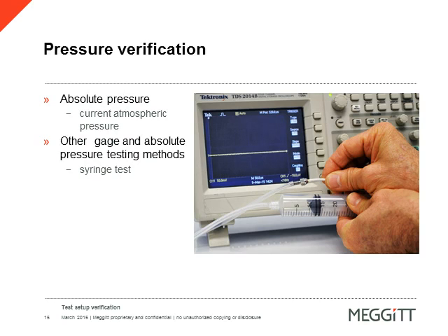For both absolute and gauge pressure transducers, a simple dynamic test method is to apply both positive and negative pressures to the sensing portion of the unit. While a syringe is the preferred method of creating pressure, it is possible to do this using simple tubing and creating pressure from your mouth. What do you think, Ray?